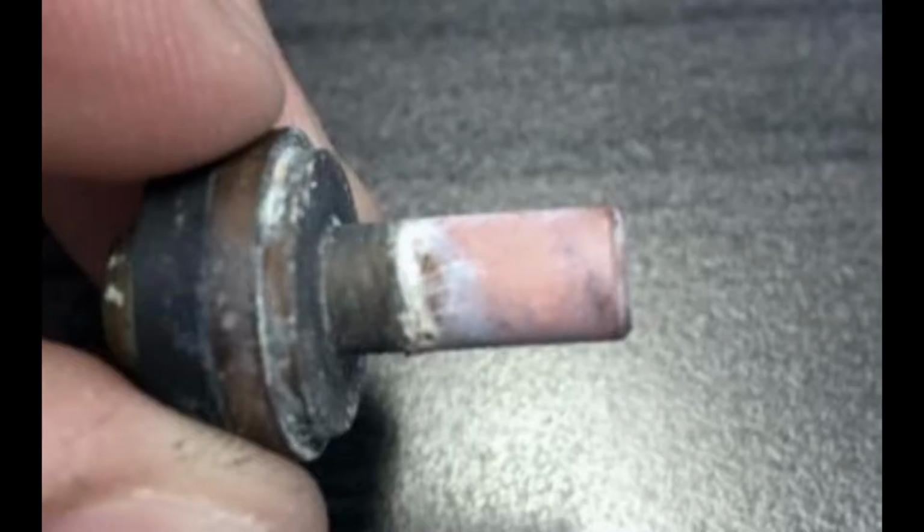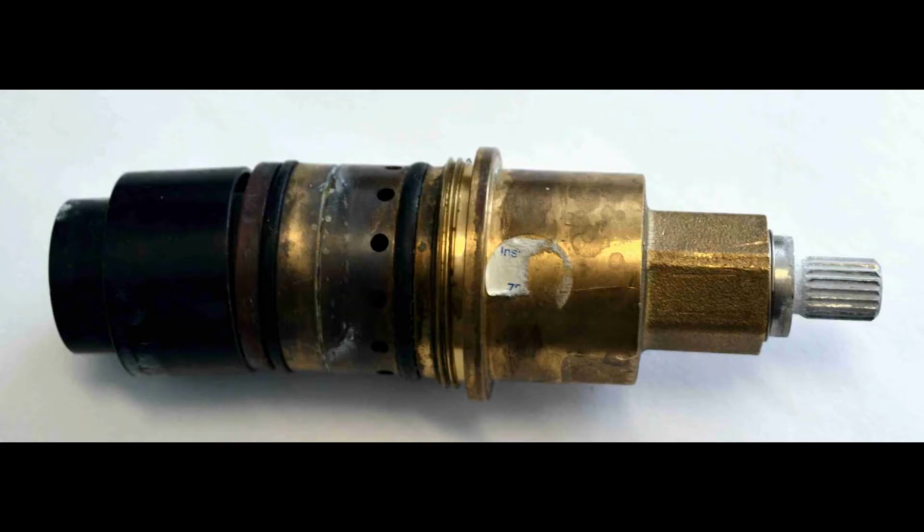The problems took root in the limescale deposit buildup on the thermostatic valve's removable parts, which had to be regularly cleaned using acid. "We had to commit 24 man-hours per week to acid cleaning the block valves and replacing defective thermostatic cartridges," said Mr. Vibert, maintenance manager, "and each cartridge replacement cost us $136."